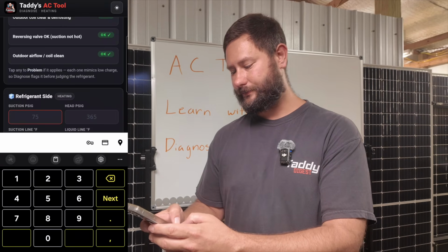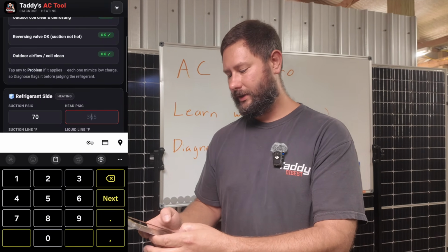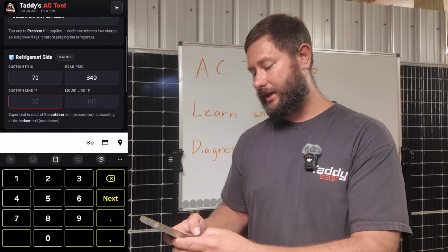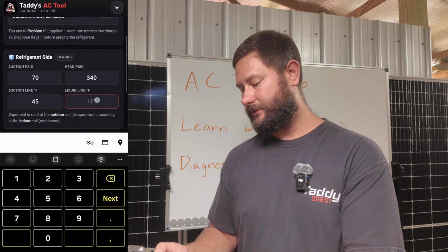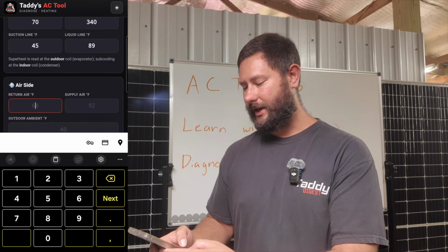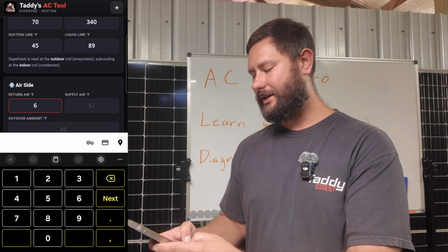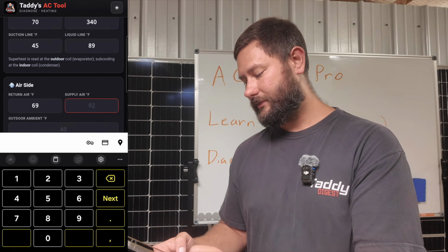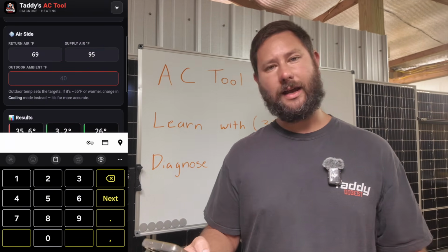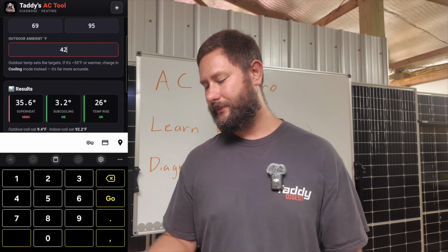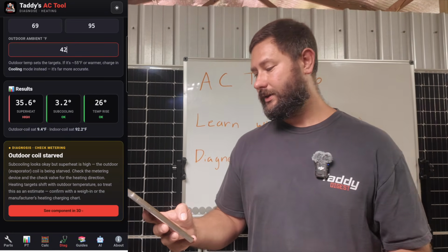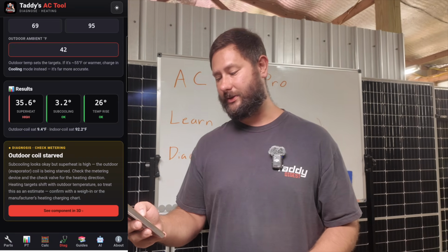Now, suction pressure. Let's say it's 70. Head pressure is 340. Suction line, let's say it is 45. Liquid line, 89. Air side, let's say return is 69. Supply air, let's say it is 95. Outdoor ambient, let's say it is 42 degrees outside. Superheat, high. Subcooling, okay. Temperature rise, okay, 26 degrees.